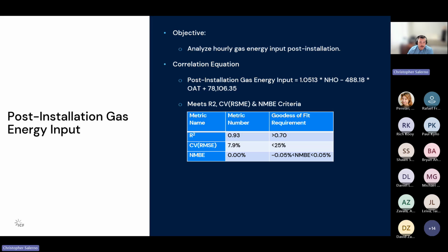So here is actually the post system gas input. This is the system that I showed on the previous slide with the GHP integrated. This gas input considers the input to both the boilers and the actual GHP itself. But the output of the system is the same, since it's receiving the same input from the return cold water, and it's still supplying the same hot supply energy. So essentially you're only inputting now an extra source of gas, which should be much more efficient ideally. These were analyzed on an hourly level. We collected them on a minute basis, but we analyzed them hourly. And you can see here that the post system was also related to the OAT and the NHO, the net heat output, and the OAT, outside air temperature.